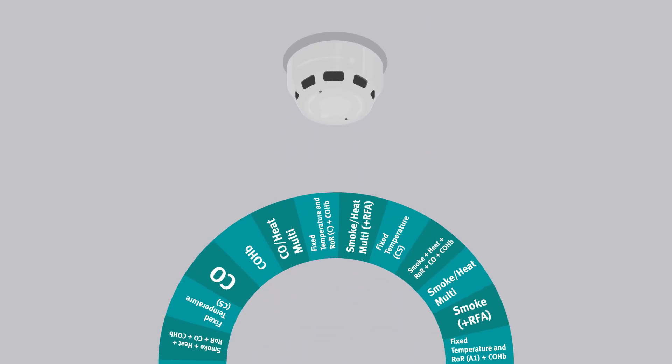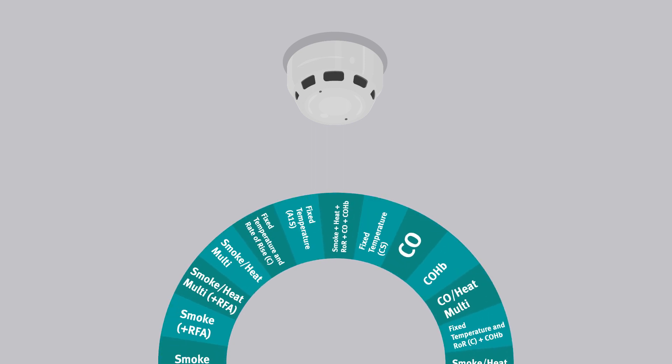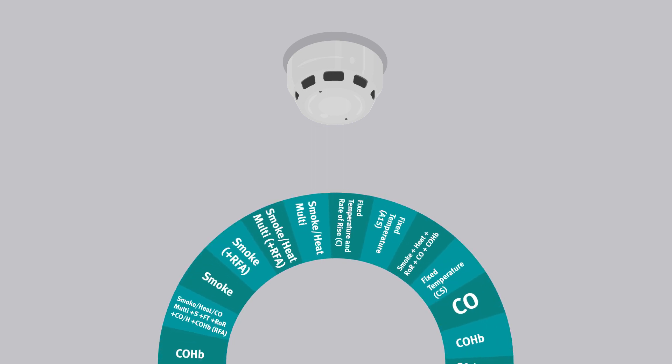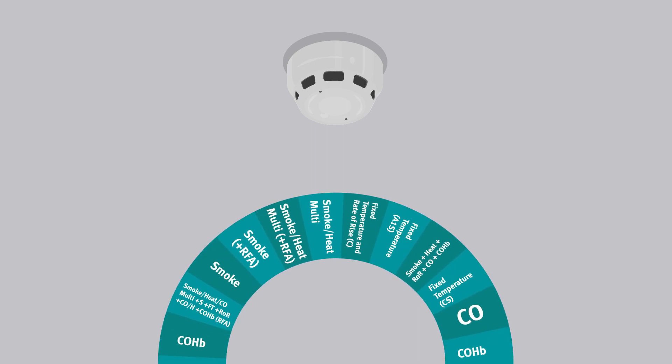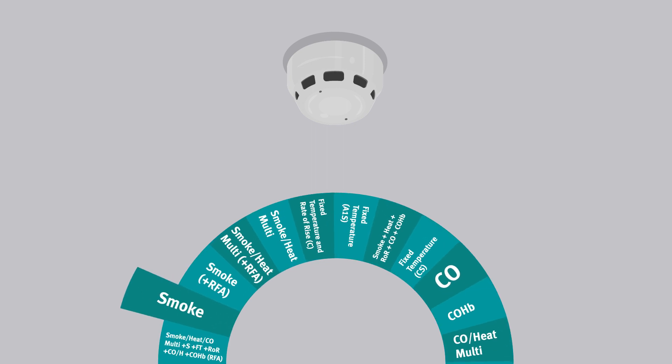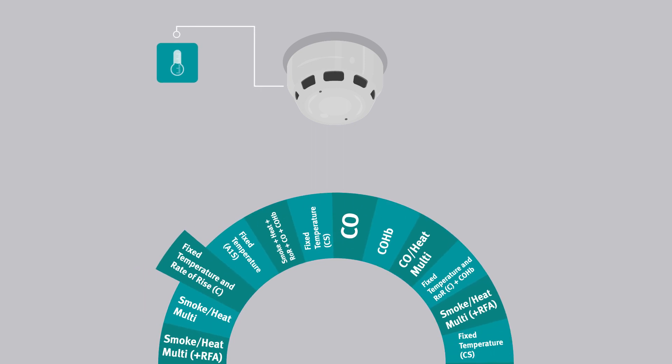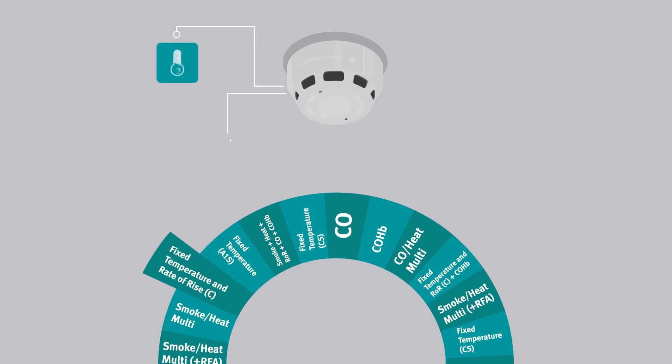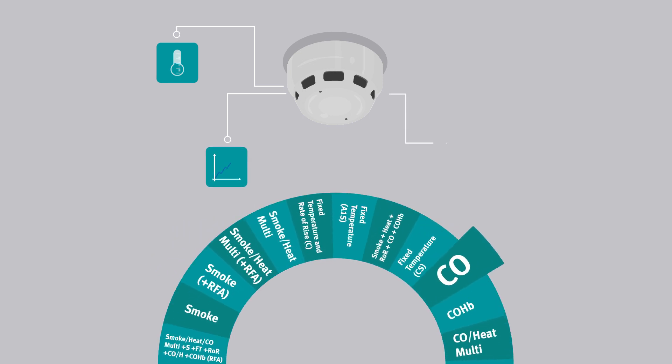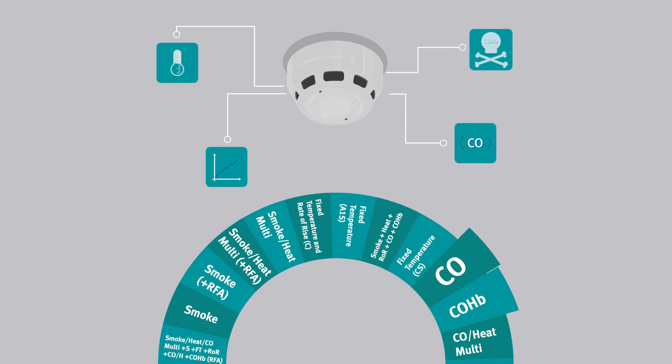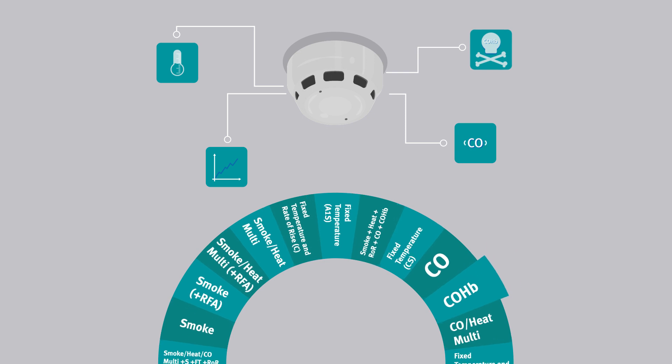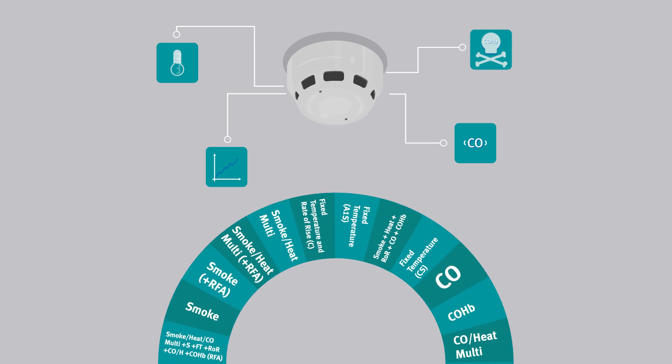This revolutionary product offers a staggering 16 UL approved modes of operation, including combinations of smoke detection, fixed temperature heat detection, rate of rise heat detection, CO detection, and COHB toxicity recognition, making it ideal for a broad variety of applications.